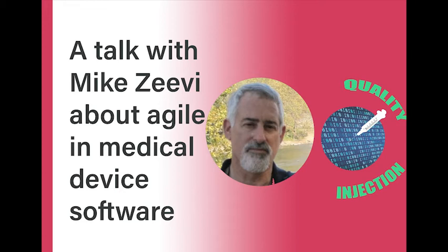Now, when it comes to talking to the FDA or dealing with medical devices, I have no problem people calling their development process agile or anything else, as long as they know that requirements have to be defined and they have to be approved, and they have to be traced back to. Your architecture and design should not change as you move along, and you have to validate the system, the version at the end of your process.